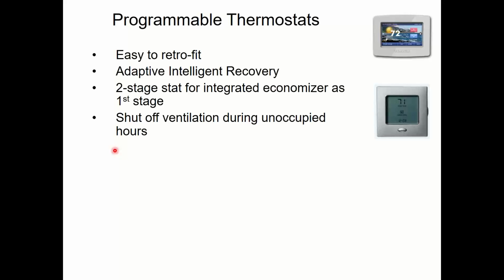Now, maybe you want to start the ventilation a little bit early. That's fine, right? But I don't want the ventilation to go all night long. There's no reason to ventilate at 2 in the morning when no one's there. This is required by code now. I would say less than 2% of the buildings I've been to have had this, whether it's code compliant or not. And it's super easy to do. It's a thermostat that, once again, costs like 10, 15 bucks more than other thermostats, and it's an extra wire.